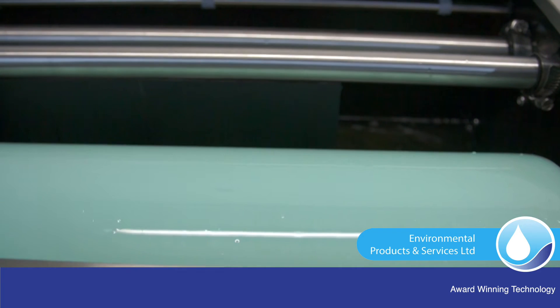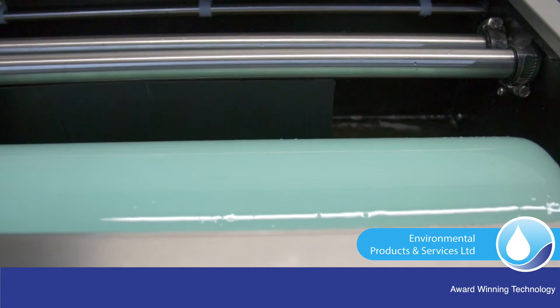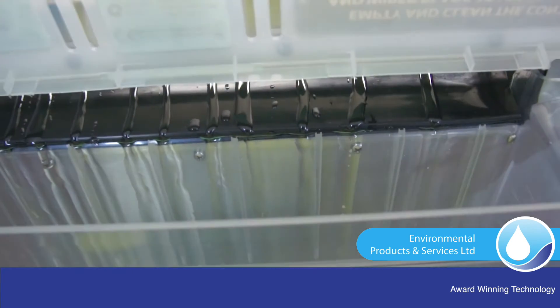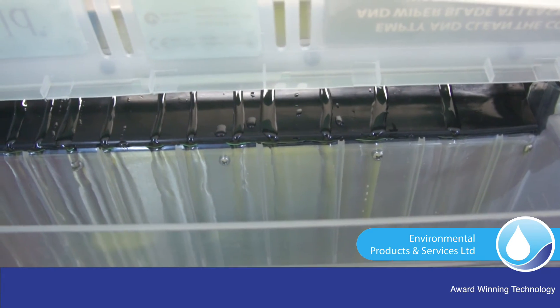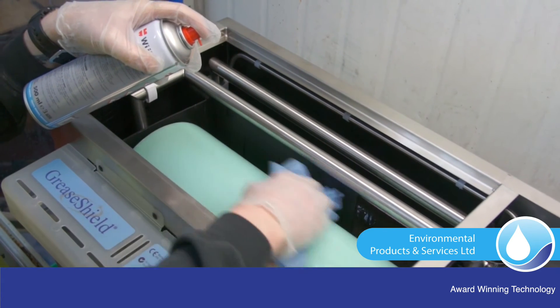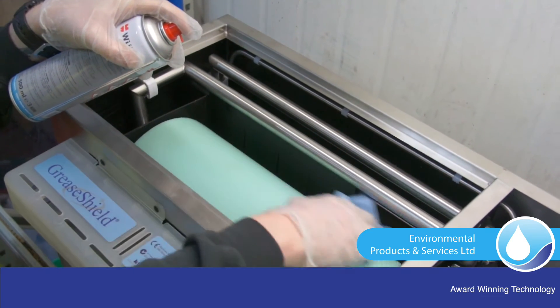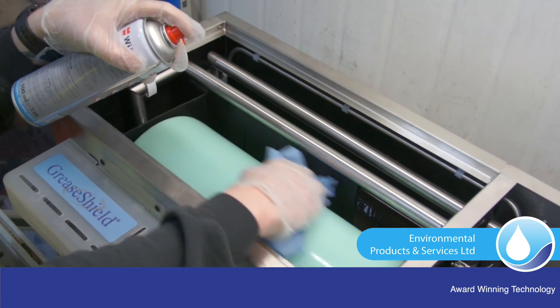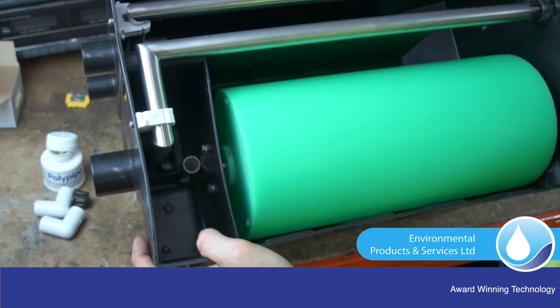The FOG removal means comprises an oleophilic and hydrophobic roller which attracts FOGs and repels water, working in cooperation with a long-lasting wiper blade having anti-static properties. No maintenance is required for the FOG roller, but if touched by hands it must be cleaned with washing up liquid and a clean damp cloth. The FOG roller is wiped by a long-lasting silicone rubber blade with anti-friction properties to prevent static build-up.